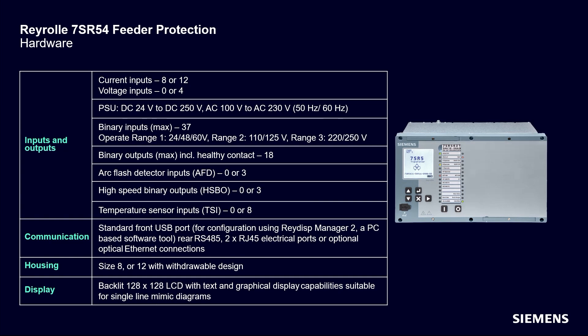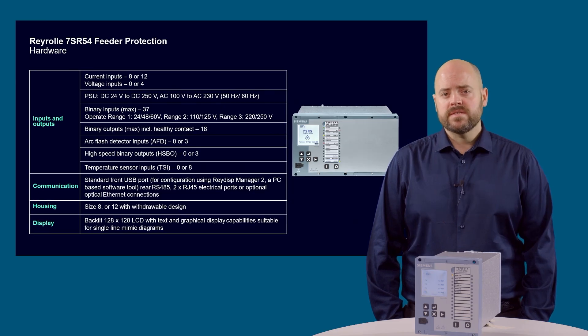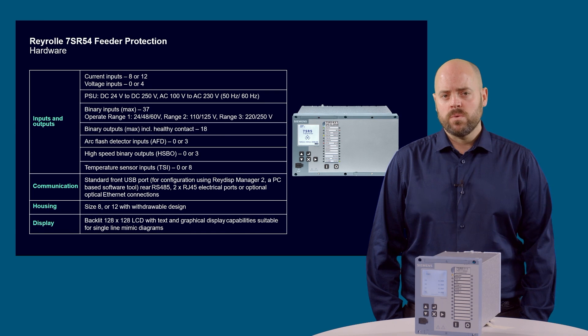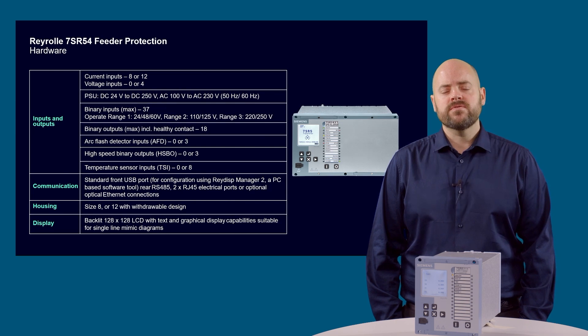The device has a rear RS485 port and dual Ethernet ports with either electrical or optical interfaces. Communication protocols include IEC61850, Modbus TCP, DNP3-TCP, and redundancy protocols. The smaller S8 devices have a case width of 205mm and the largest S12 is 308mm wide. A large graphical display makes it easier to view device information.